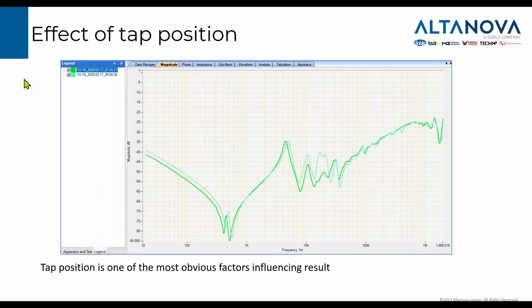Another obvious effect that can be seen in SFRA responses is tap position. If you look at your trace measured at 2 different tap positions, you would normally see differences in the medium frequency range. So when you measure your transformer and you don't get a good comparison with reference results in this region, maybe you should think about tap position. Maybe you have the wrong tap position during the test, or the reference was measured at a different tap position, and therefore your test is not matching the reference, and this is why you have difficulty in interpretation.